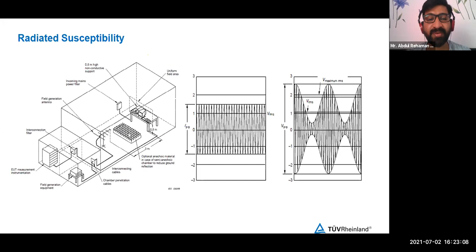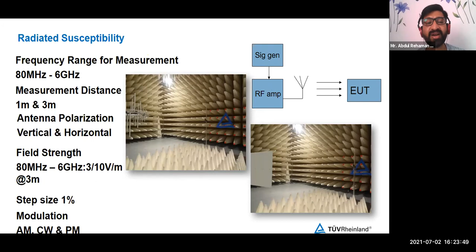The standard says the minimum distance should be 1 meter. Above that you can have whatever distance you want, because here the intention is that the noise being generated by the antenna has to get injected to the DUT. Here the functionality of the DUT is most important. Here we have an amplitude modulated signal, continuous wave, and pulse modulated signals; these are the different modulation methods which are injected for radiated susceptibility.